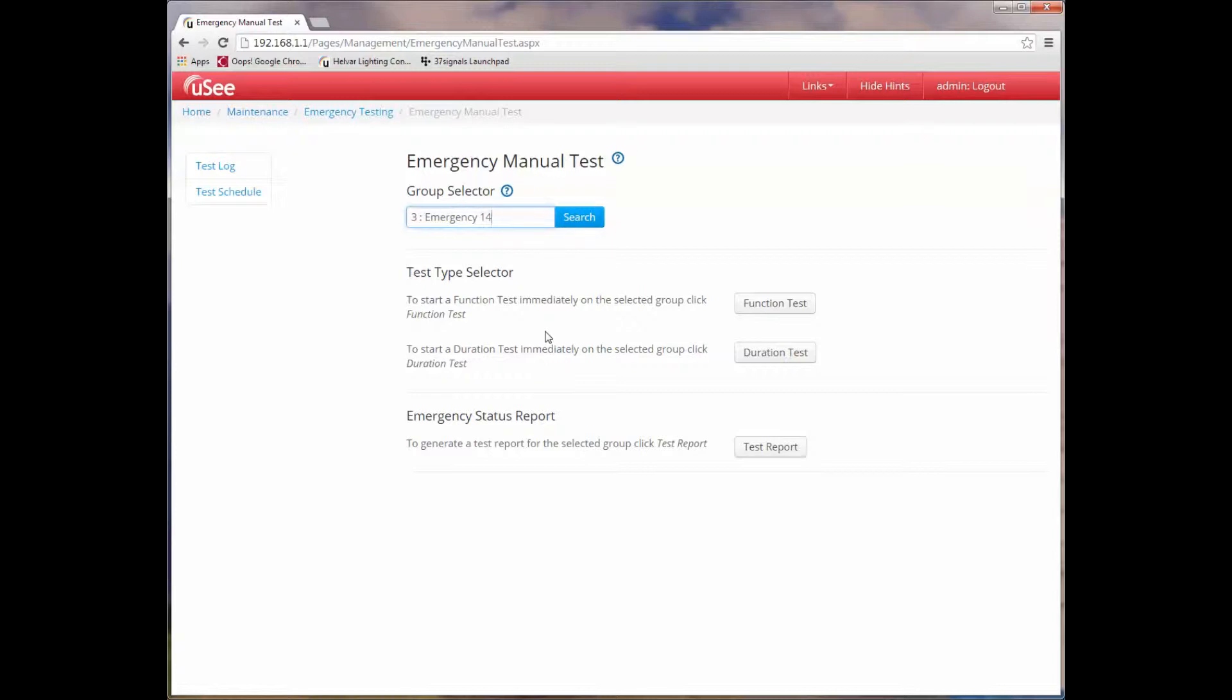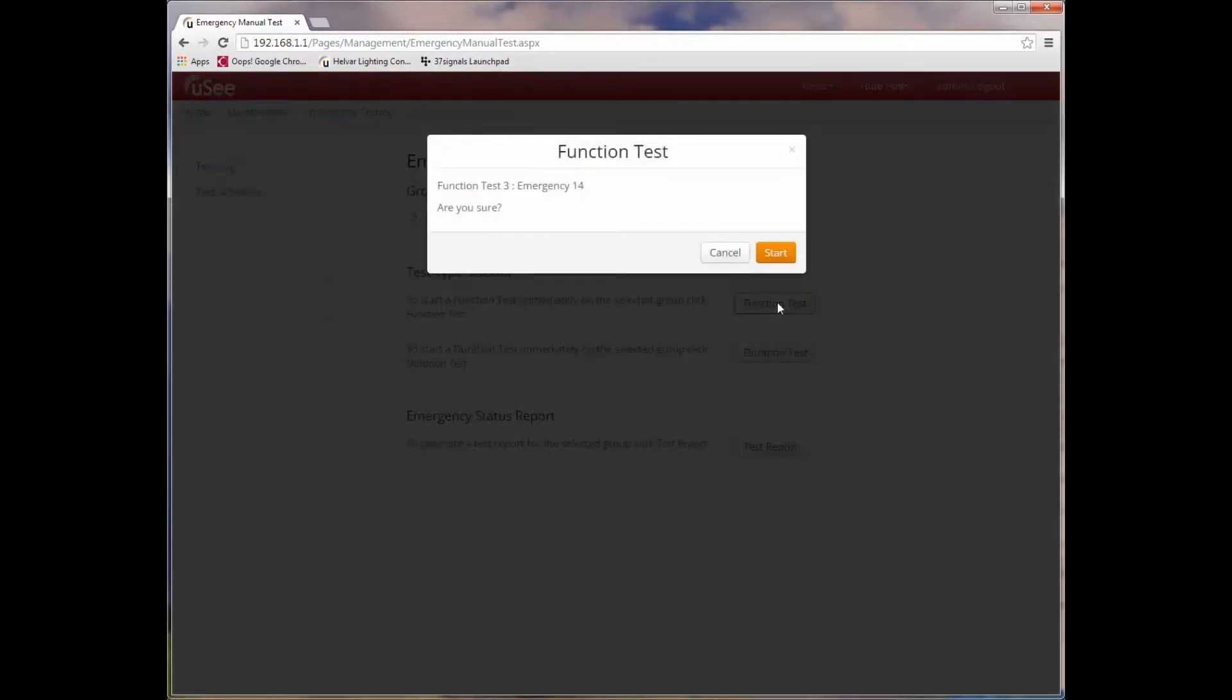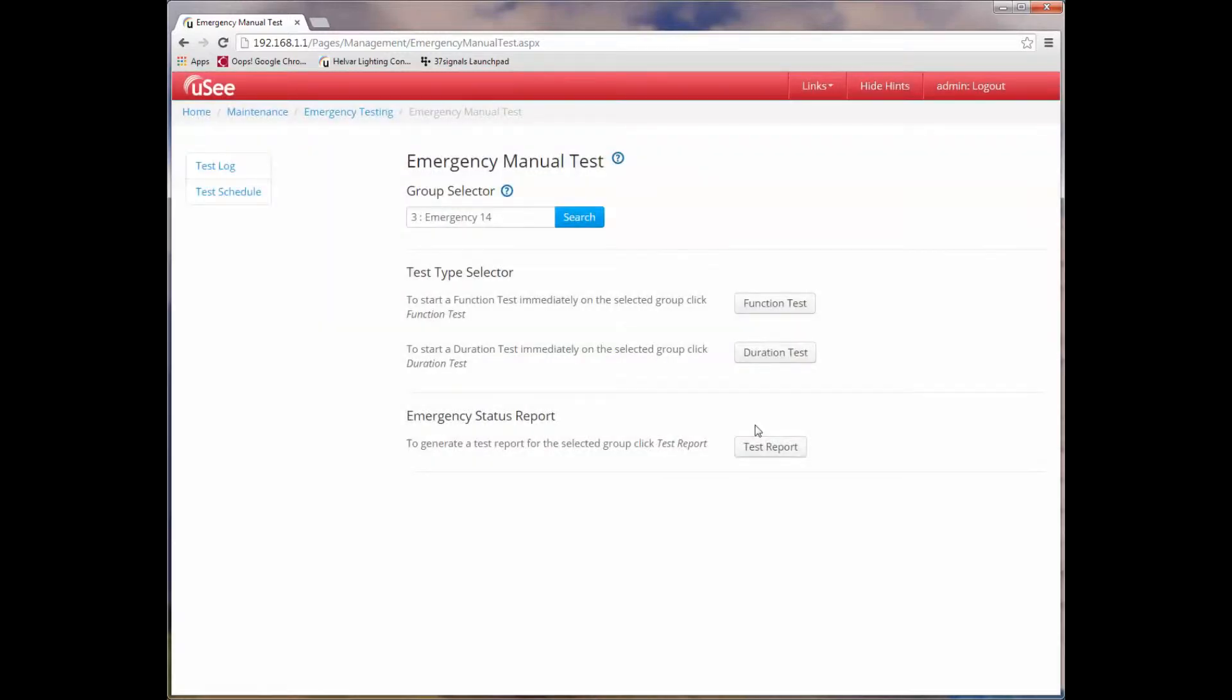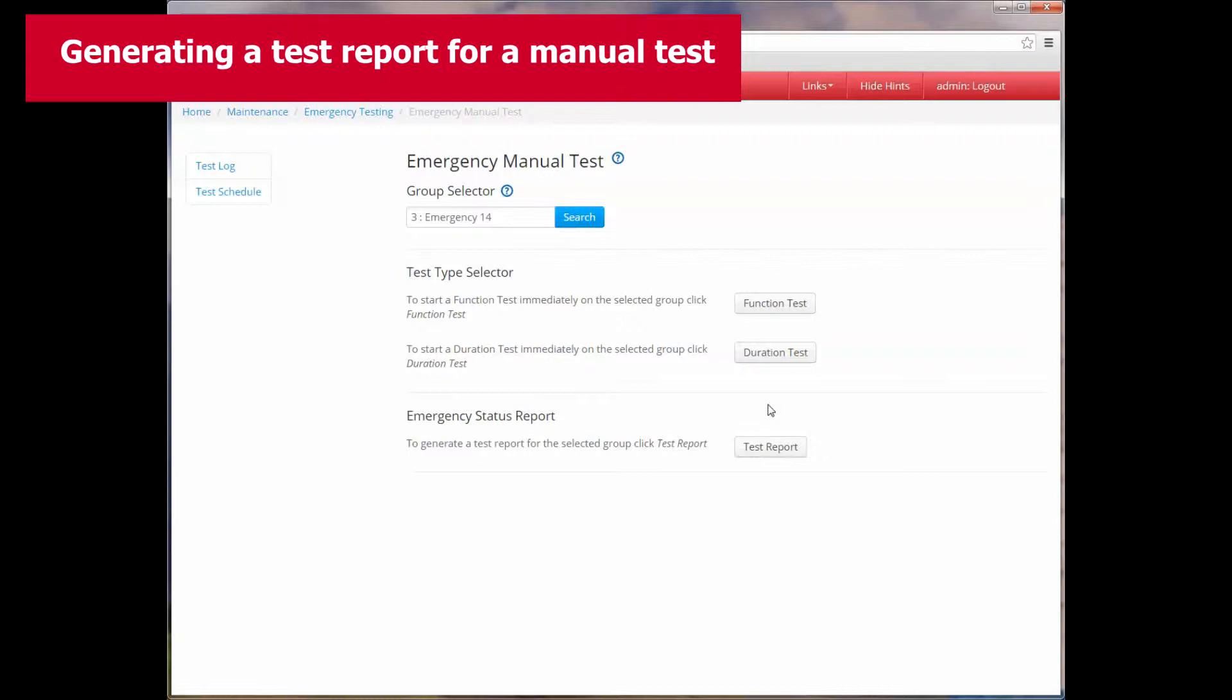Let's select group 3 which is named emergency 14. Quite simply we're going to start a function test on this by clicking on the button. We get a dialog which confirms whether we want to start the test or not, and we are going to start the test. Now the time taken to execute a function test varies. With some devices this might take up to a minute. The particular device we're looking at takes approximately 30 seconds.